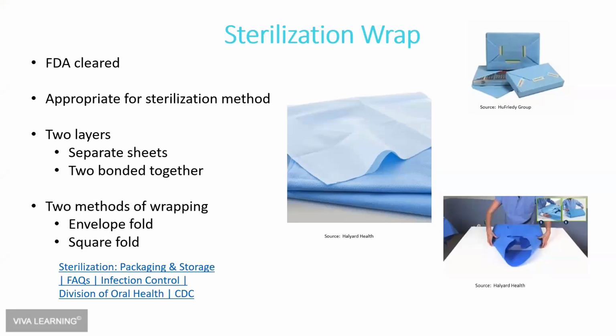We have another question: are wraps single use or reusable? They are only single use, just like sterilization pouches. You cannot reuse them, because once they've gone through a sterilization cycle, the pores on the material will open and close depending on the steam and the pressure and so forth in the sterilizer, it won't be successful again. It's only meant and only tested and approved to be used in one cycle, and they're much more subject to tearing. They may have already been torn when you open the packages, so we don't reuse them.